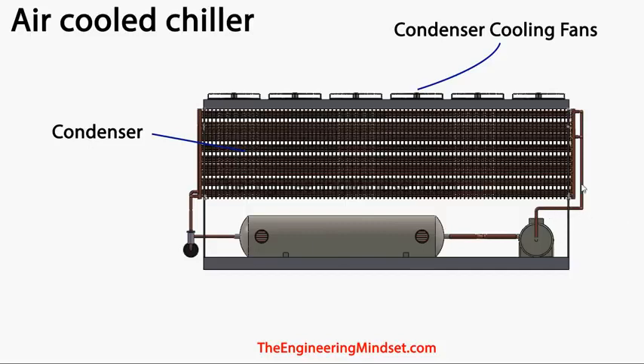So the hot refrigerant is coming from the compressor, and it will pass through the tubes within this condenser. And you'll see there's a number of loops. We'll have a look in detail at how that works shortly, but it will pass through here and make its way out and then into this header here. And by the time it leaves the condenser, the refrigerant will be a high pressure, medium temperature, saturated liquid.